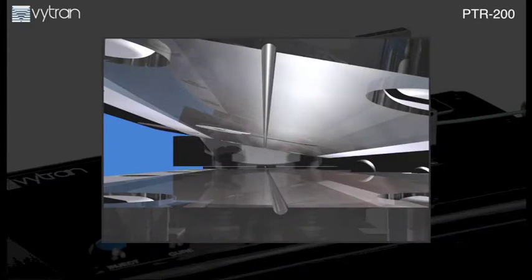Our PTR-200 recoaters use split quartz mold plates which, when closed together, form a circular mold cavity around the exposed section of the fiber.